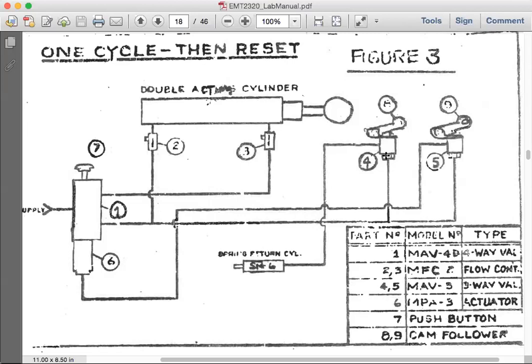There is still pressure at the bottom, but this pressure from the left side vents through the hole in the stem, meaning the piston from the spring return cylinder is retracting fully back into the cylinder. So the spring return cylinder already completed 1 full cycle.